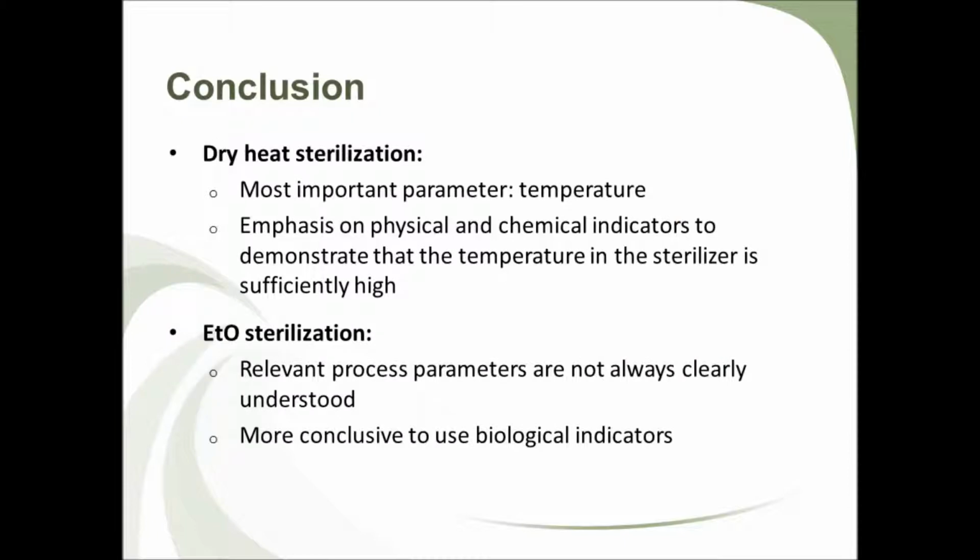In conclusion, temperature is the most important parameter to monitor for dry heat sterilization, and thus there is a greater emphasis on physical and chemical indicators to demonstrate that the temperature in the sterilizer is sufficiently high for the correct amount of time. In contrast, biological indicators are more reliable for ETO sterilization because relevant process parameters are not always clearly understood. Carrying out a biological test would be more conclusive in determining if sterilization is performed appropriately.